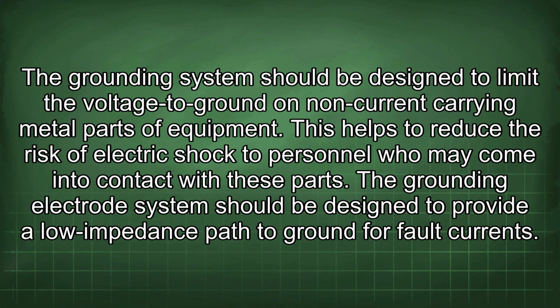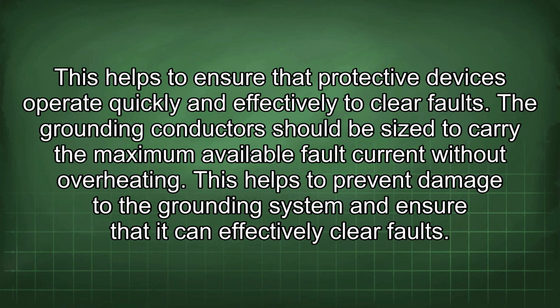The grounding system should be designed to limit the voltage to ground on non-current carrying metal parts of equipment. This helps to reduce the risk of electric shock to personnel who may come into contact with these parts. The grounding electrode system should be designed to provide a low impedance path to ground for fault currents. This helps to ensure that protective devices operate quickly and effectively to clear faults.